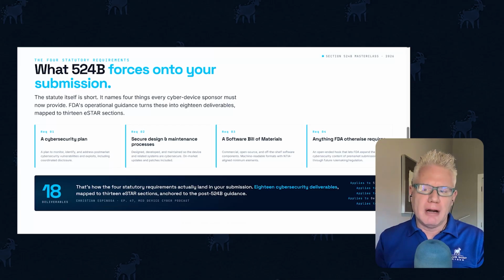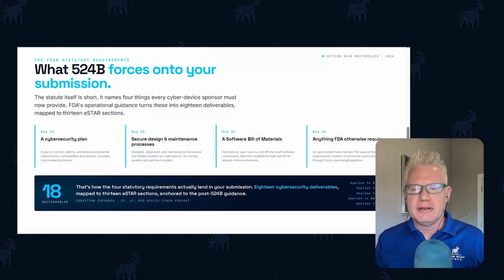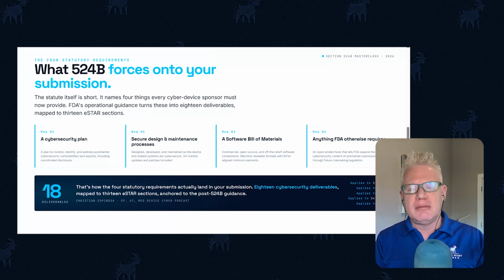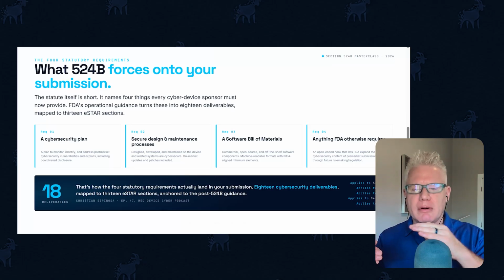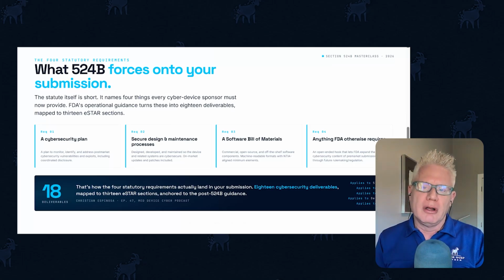And then requirement number 4 is just an open-ended requirement that says if the FDA decides to add something else, then it still falls under 524B, and you're required to do that from a cybersecurity perspective. And at Blue Goat Cyber, we have 18 deliverables that align with a pre-market submission. Some people have less than 18, but we do the 18 to make sure we hit every requirement for the pre-market submission that aligns with the February 3rd, 2026 guidance.